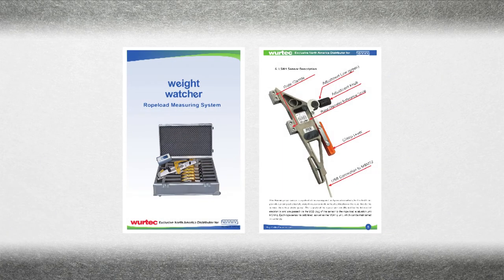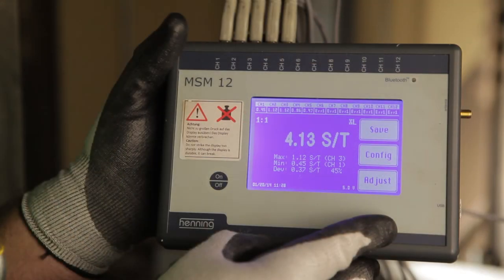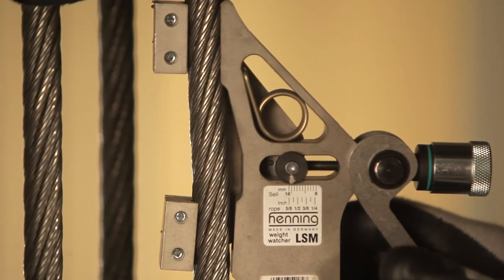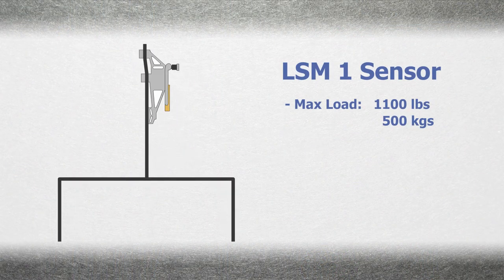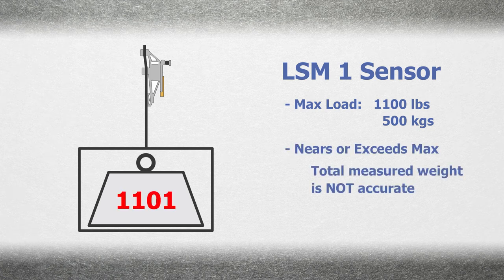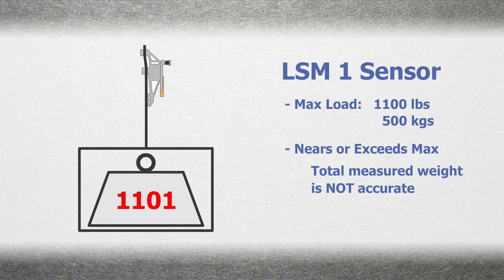For further information, refer to the Mobile Weight Watcher User Manual at www.wurtec.com. Pay attention to the measured weight displayed for each individual sensor. Be sure that the measurement is not greater than the maximum measurable load for the sensor. For example, LSM1 sensors have a maximum measurable load of 1,100 pounds. If the individual sensor weight nears or exceeds 1,100 pounds, the total measured weight of the car will not be accurate.